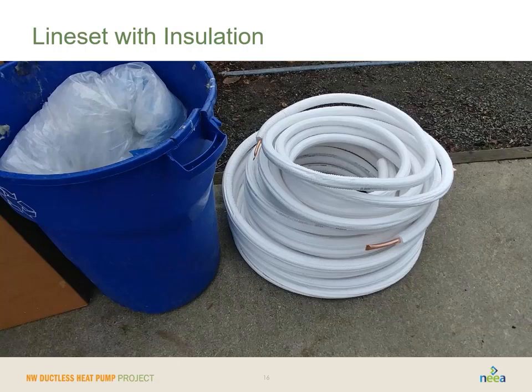This is the line set, or that refrigerant tubing, and it's already got insulation with it. This is how it typically is shipped, and so we want to make sure that when we install this line set, or these refrigerant lines, that we really do have quality insulation covering it all the way from the compressor to the indoor head. This will ensure that we actually get the heat to transfer where we want it to go, and it will prevent condensation on these lines, which can always be a challenge.